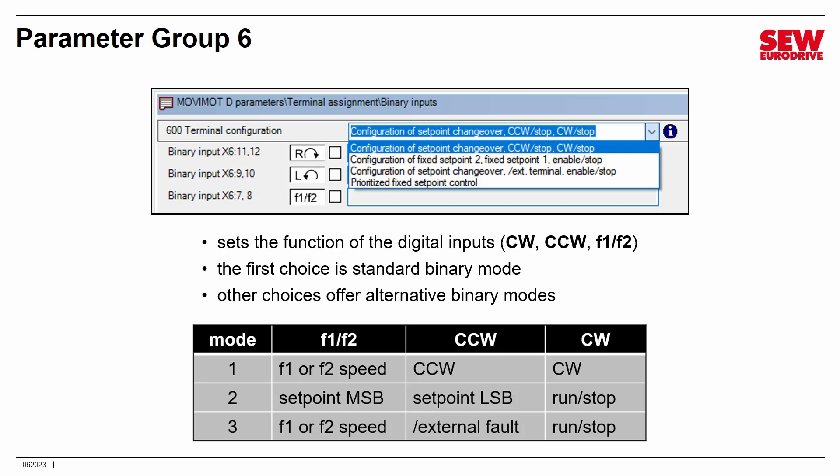A slash in front of 'external fault' indicates it is an active low digital input — if you want to signal that a fault has occurred, you provide a low signal near ground level; to indicate everything is fine, you set it around 24 volts. This is opposite to how normal control signals behave, and it's a safety feature: if something goes wrong, a wire gets cut or disconnected, or the power supply fails, it creates a fault situation that puts the drive in a safer state.